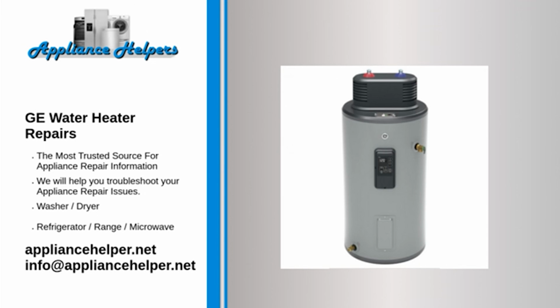Water heater is too hot. The thermostat determines the maximum water temperature setting. If the thermostat is defective, the water temperature may not be set at the proper level. To determine if the thermostat is defective, assess hot water temperature from the nearest faucet. If the water temperature is hotter than the selected thermostat setting, this indicates that the thermostat is defective. If the thermostat is defective, replace the gas valve and thermostat assembly. We recommend a set temperature of 120 degrees or fewer to prevent the risk of scalding.